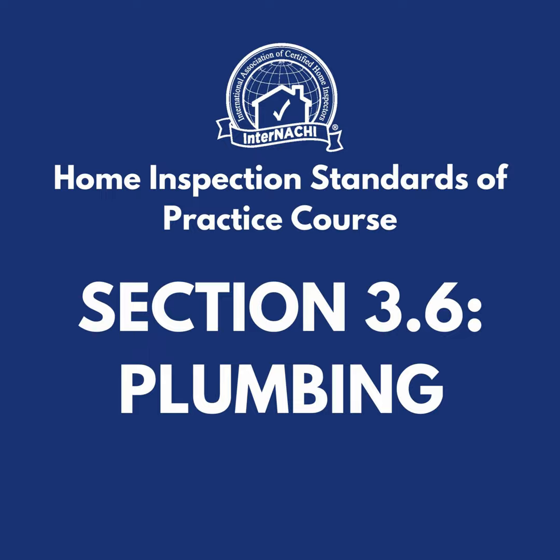Home inspectors are required to inspect the water heater's temperature pressure relief, or TPR valve. The 2018 International Plumbing Code describes more than 12 requirements that a TPR discharge piping must meet, according to 2018 IRC 504.6. The inspector is not required to operate the TPR valve, but it needs to be present and it should have a proper discharge line and termination. Because a TPR valve may be filled with corrosion or debris, the operation of the valve may cause the valve to open and not close back again. Home inspectors should not operate any valves, including shutoff and TPR valves.